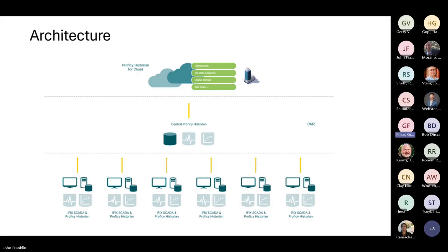Yeah, I guess like you mentioned the part with the historian on for the SCADA, and then the one in the cloud, so to speak. I think that's sort of like the store and forward, is what you're using there, right? So that if you lost connection, it'd still collect, and kind of a form of redundancy. Correct. And then just the collectors themselves, the collectors will store. And so even if the historian at the plant is down, the collector's still doing its job. Right. And so when it comes back online, it'll have to backfill.